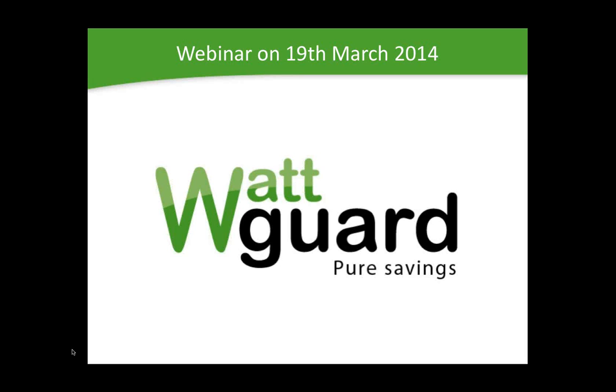Thank you, Mr. Christensen. Is this technology available for LEDs only, or only conventional tube lights? It is not available for LED or for any technology that has electronic ballasts. So it's available for conventional types of lighting. That would be the types of T8s, or metal halide, or CFLs, or sodium vapor, or any other type of light unit that is controlled by a conventional starter.